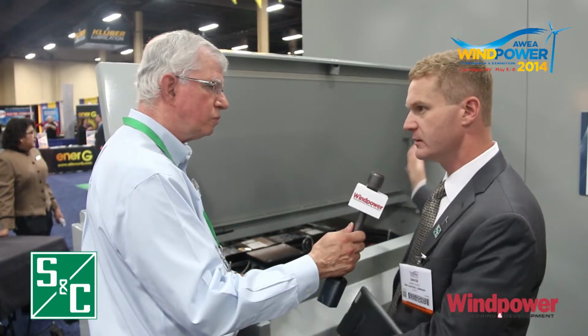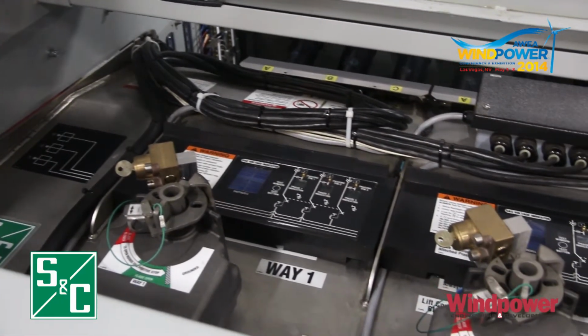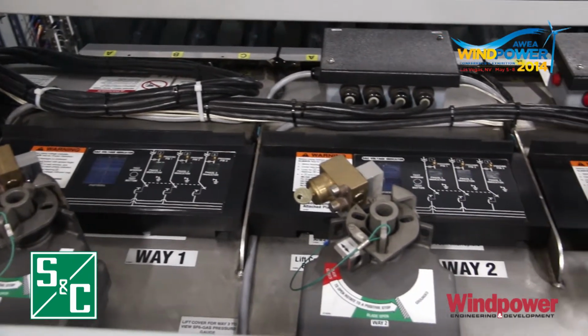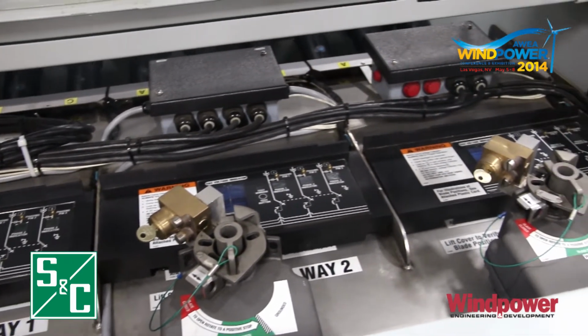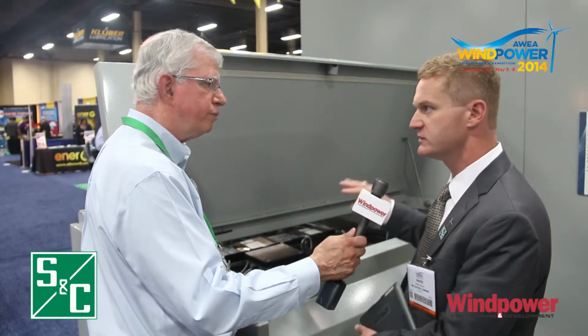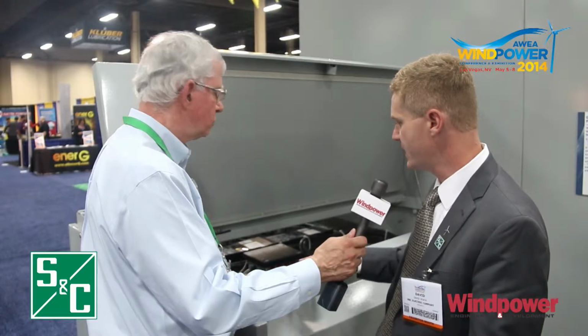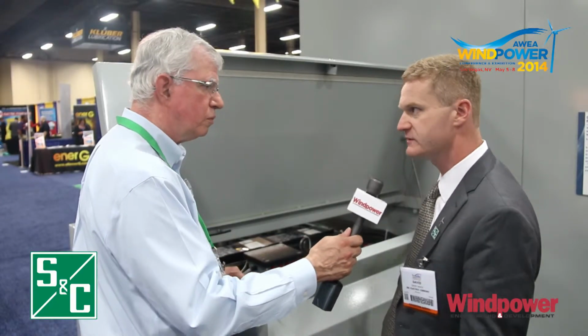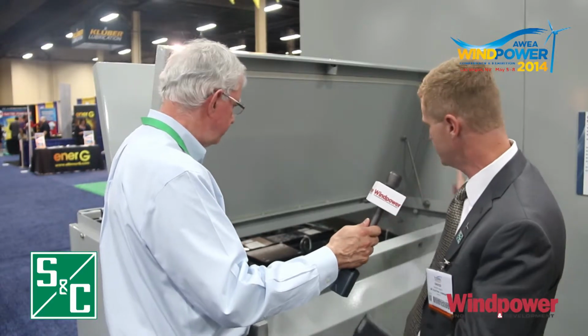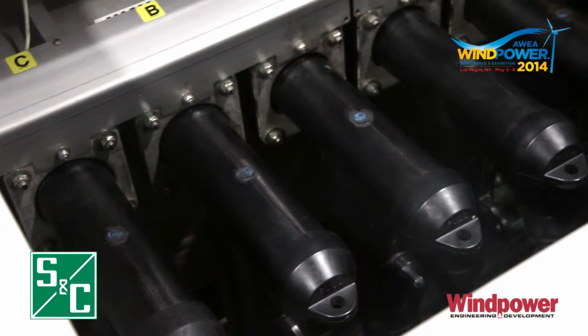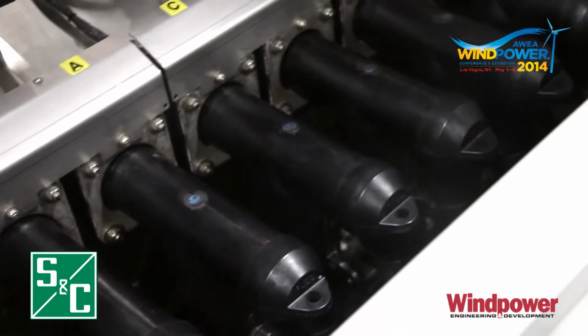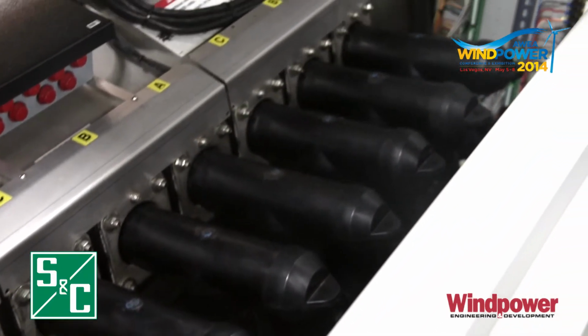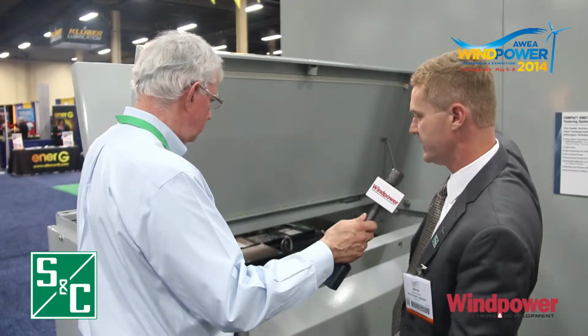It reduces the footprint of the substation. It puts it in one complete enclosed package, and it also greatly reduces cost. It reduces lead time and on-site construction, because this comes out of our factory manufactured, put together, tested, and all it needs is to be placed on a pad with some terminations made, and it's ready to go. So what it does is combine - this front end here is another piece of Vista switchgear. It's a typical setup where we married our Vista switchgear, an SF6 gas-insulated switchgear at 35 kV, to a typical air break switchgear lineup as well.